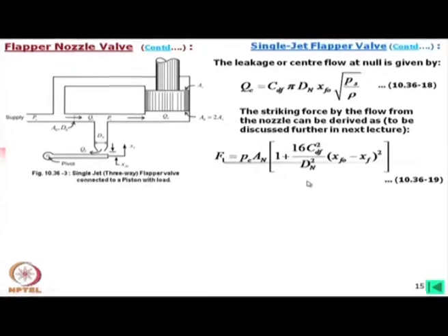Now, what is striking force? The striking force means this: when the flow is coming on, then this is striking on this flapper, which is ultimately required to estimate how much torque is required. Okay. So, this F1 is estimated by this formula.